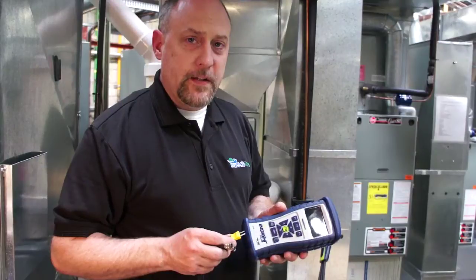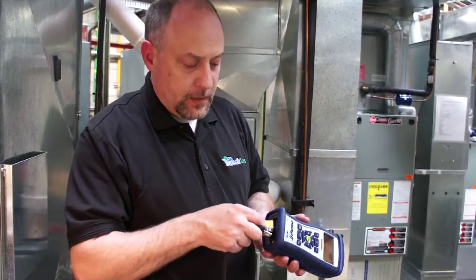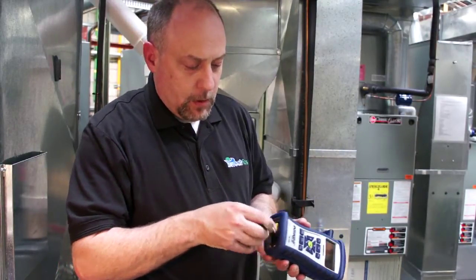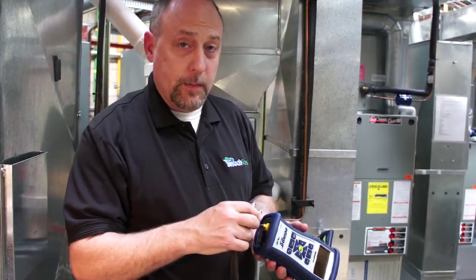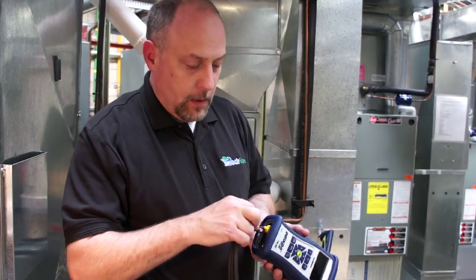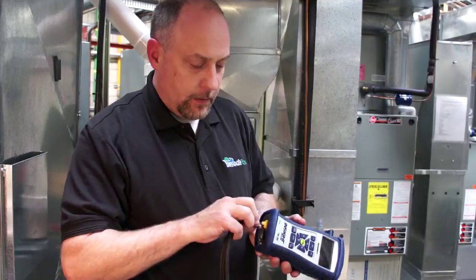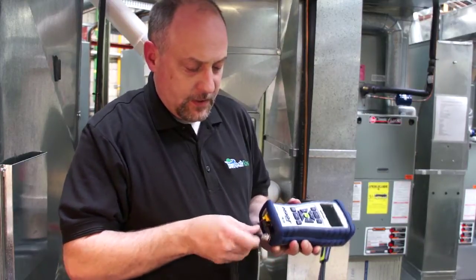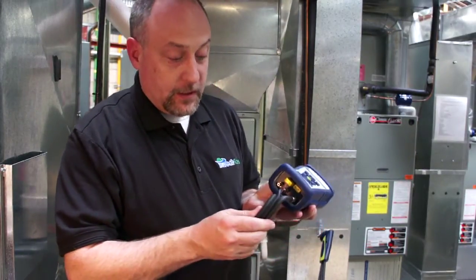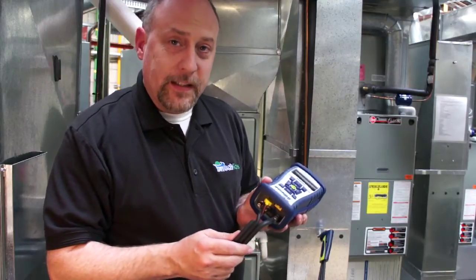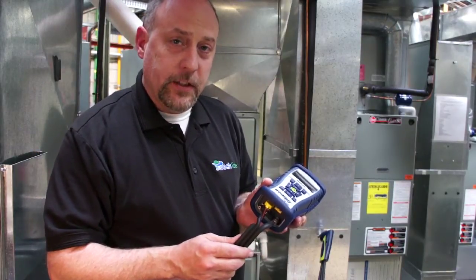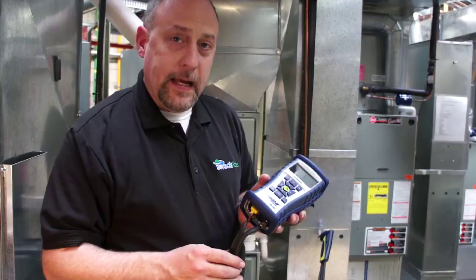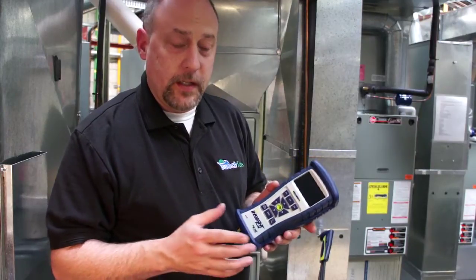All right, when we configure the INSIGHT Plus, really what we want to do first is plug in our K-type thermocouple, and that is polarized, so you want to make sure you put the plug in correctly. Plug in our draft and plug in our gas sensor port in the bottom, just like this. The reason you want to plug these in first is because the instrument actually goes through a self-diagnostic and a calibration when you turn the instrument on.